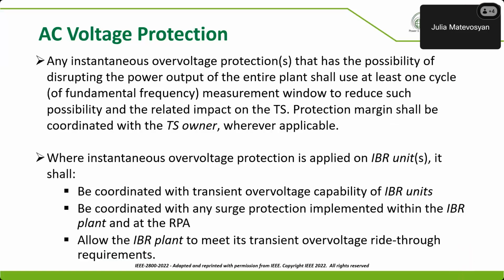Any instantaneous overvoltage protection that has the possibility of disrupting the complete plant output shall use at least one cycle measurement window. So this is if someone decides to apply instantaneous voltage protection at the point of measurement, right? If that protection element misoperates, you risk losing the entire plant.